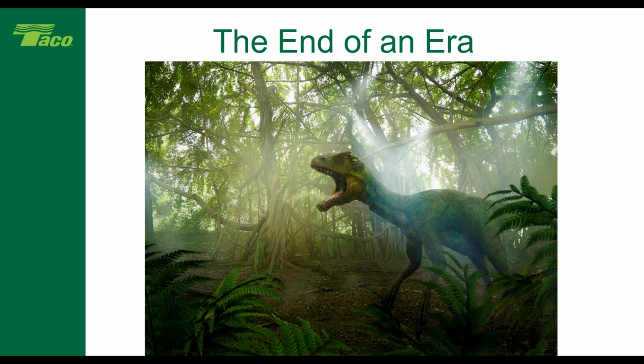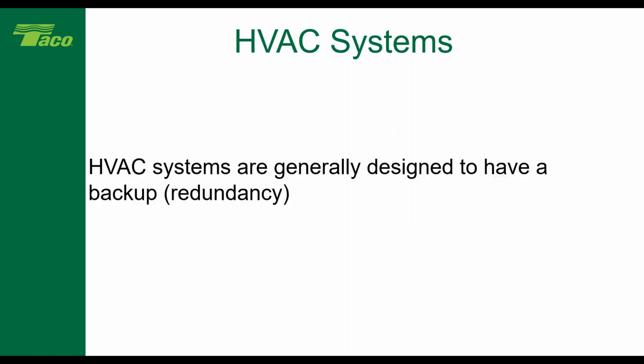One thing we've always done in the pumping world is duty standby. So we put 2 pumps in, each sized at 100%. And that really doesn't get us what we need. Yes, it gives us redundancy, but it doesn't give us the energy efficiency we need. So what I want to talk about is how do we get to where we need to be?